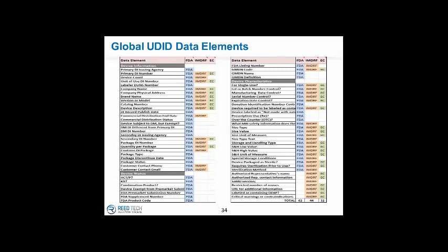And a general interest in questions about packaging and how to allocate GMDN numbers for reagents. So I don't know if there's anything global you can say there, but I suspect an email between you is in order. Yeah, I think we want to go into a little bit deeper discussions on that particular scenario. In general, there's a base product that is very important to establish at the get-go. Are there sub-elements below the base product that qualify for unit of use? And then as you have packaging levels at higher levels, if the quantity is greater than 1, you put 1 or 2 or more items together, then you need to assign device identifiers to those.